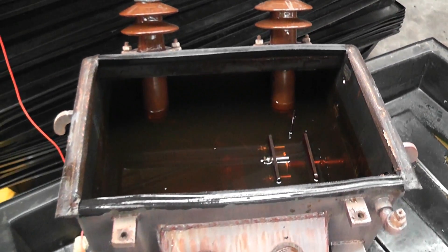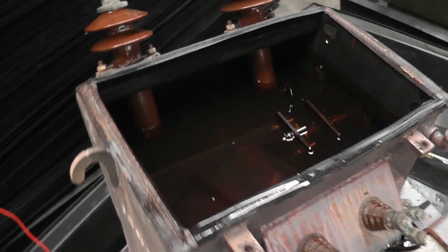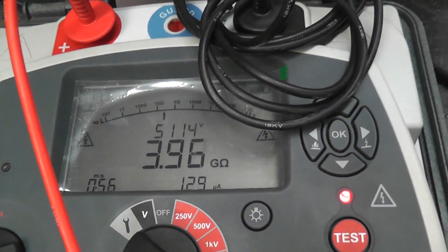Doing an installation test on an old 25kVA single-phase transformer. It has worked very hard and the oil level is low — as you can see, the gauge glasses are over the oil level. We do 500 volt tests and it's actually pretty good; it's nearly 4 gigaohms already, which is nice.